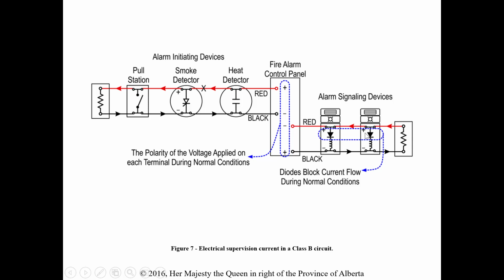And then the supervisory, it's for like a sprinkler system if it's fully operational. So again, if the valve has to be open for water to flow, that kind of stuff. So it's basically making sure that the system is ready. Those would be the other initiating devices that would potentially cause a change of state in the control panel. So it starts talking about non-addressable devices.